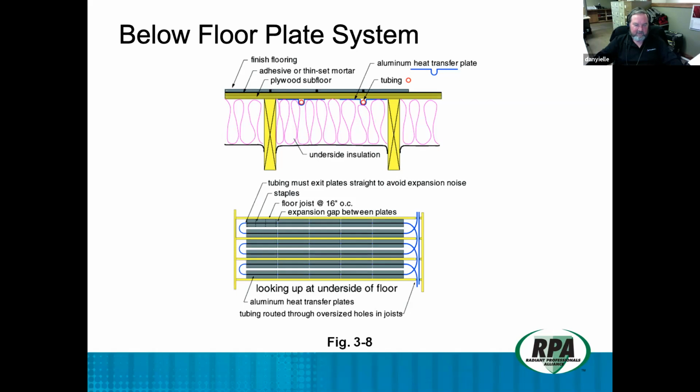And it also provides you with the temperature that you need to be able to achieve this. If you're designing a system around a ground source heat pump and you don't want any augmented heat from boilers, then you've got to make sure that the house has got high R values and that your floors or walls or ceilings or whatever you've got have enough tube density and heat transfer that it will work well with that low water temperature of 115 degrees.